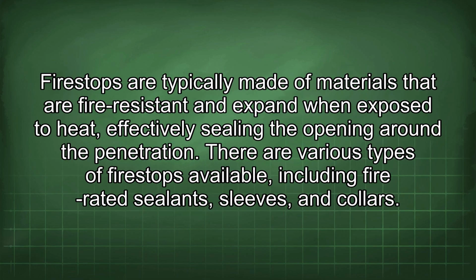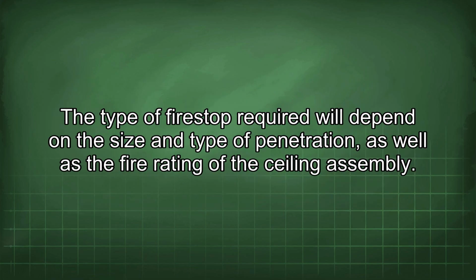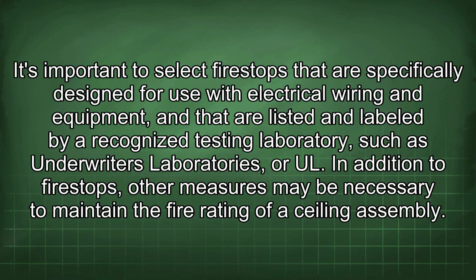Fire stops are typically made of materials that are fire-resistant and expand when exposed to heat, effectively sealing the opening around the penetration. There are various types of fire stops available, including fire-rated sealants, sleeves, and collars. The type of fire stop required will depend on the size and type of penetration, as well as the fire rating of the ceiling assembly. It's important to select fire stops that are specifically designed for use with electrical wiring and equipment, and that are listed and labeled by a recognized testing laboratory such as Underwriters Laboratories, or UL.